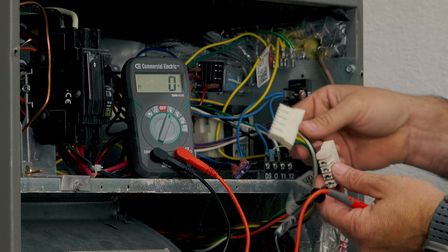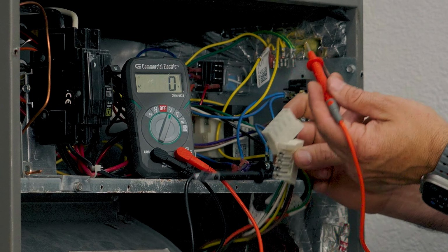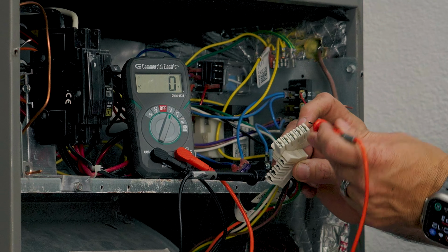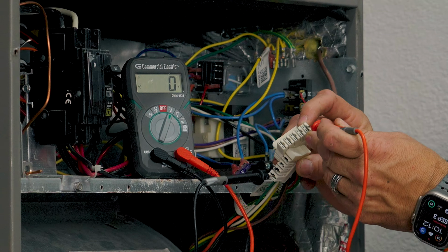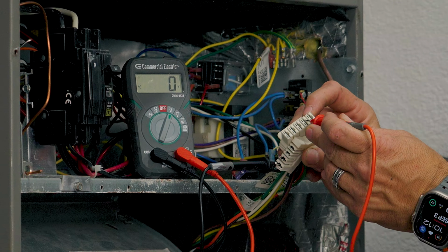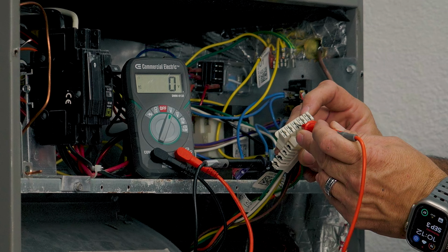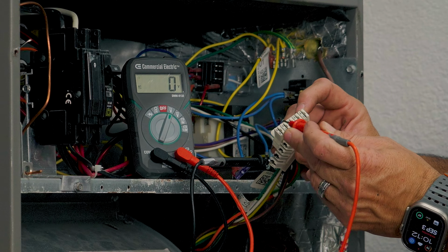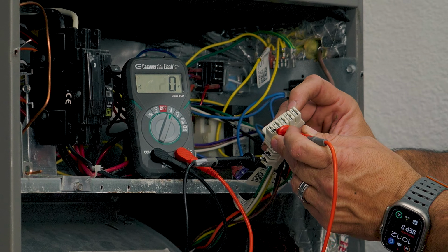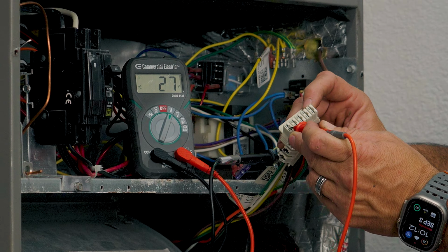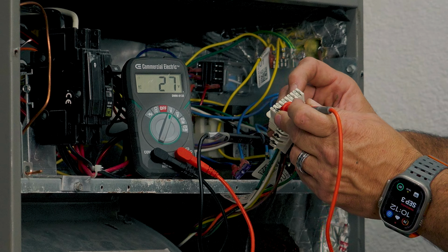We will grab the other harness, and we will test between all of these terminals and find out which one is energized. We're looking for between 21 to 28 volts AC. Here's 27 volts. We verified this has low voltage.